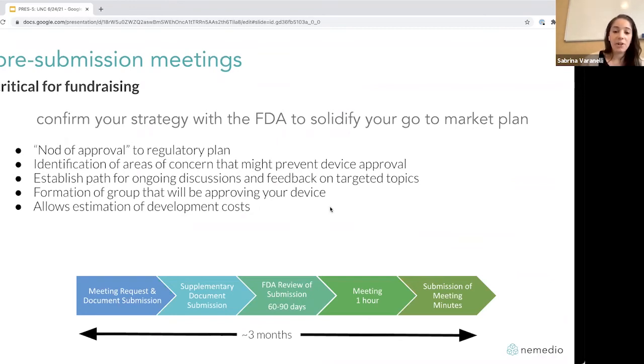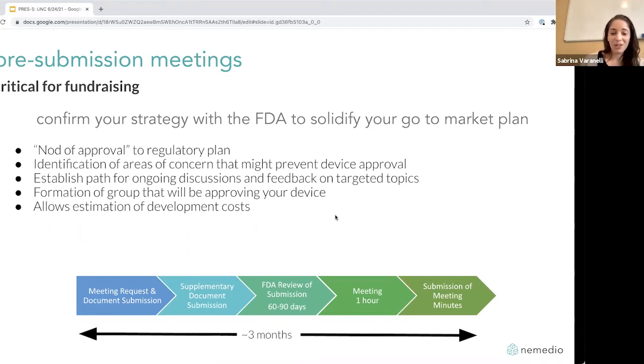Additionally, FDA is really concerned about safety. Showing them your initial risk assessment lets them point out things they're concerned about so you can address them before your final submission. FDA is essentially giving you a nod — they're not saying for sure they'll accept your device, but they're saying 'we agree with your plan and think you're on the right track.' It's also interesting that the people grouped together from the FDA for your pre-submission meeting are usually the same people who will read your final submission. So it's a great opportunity to get face time with them, build a relationship, and get their contact information.